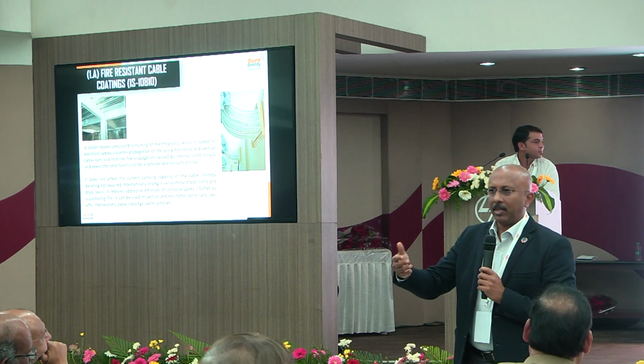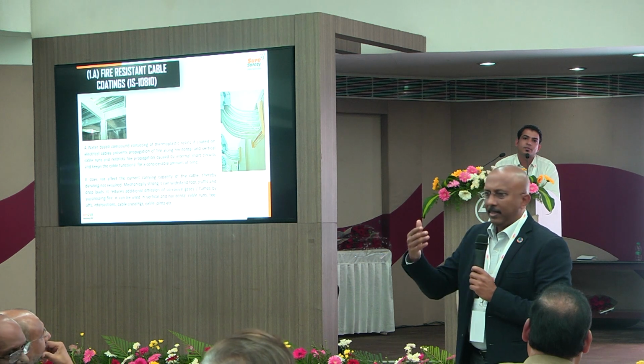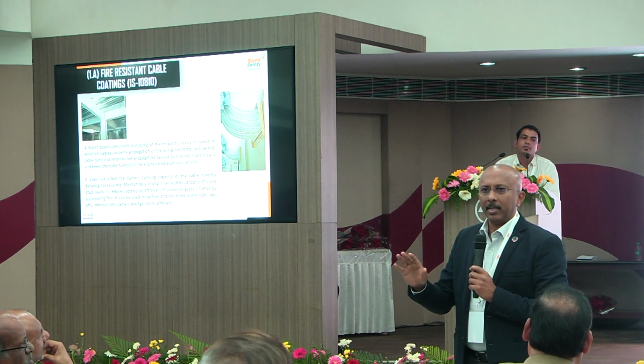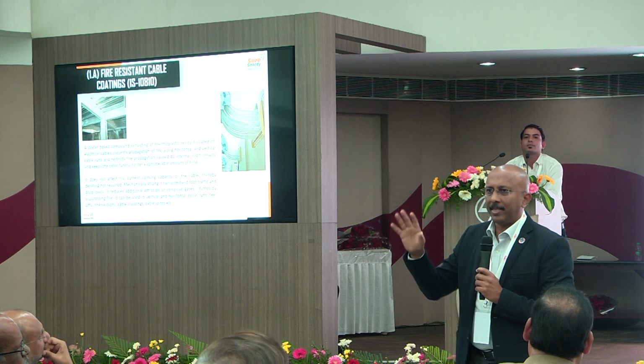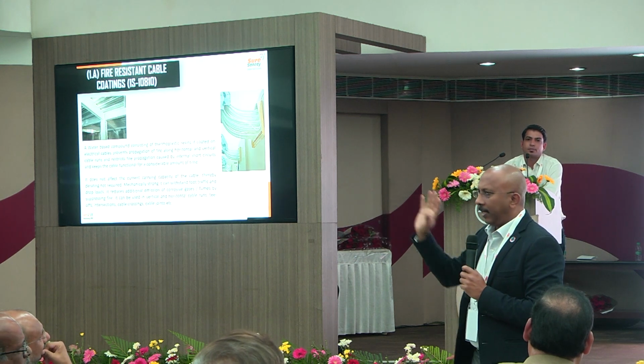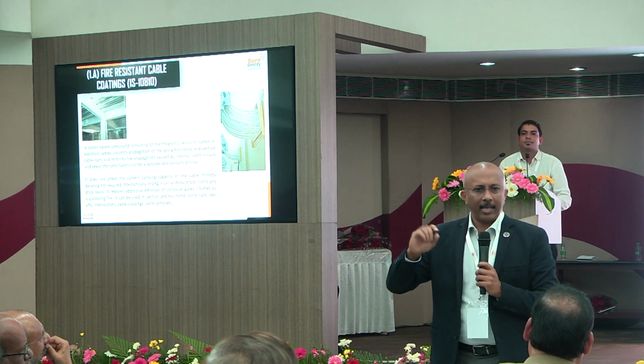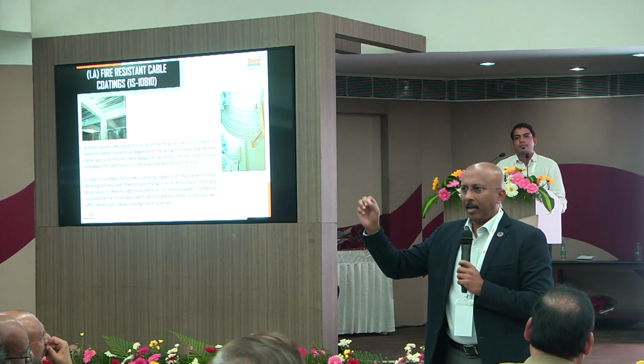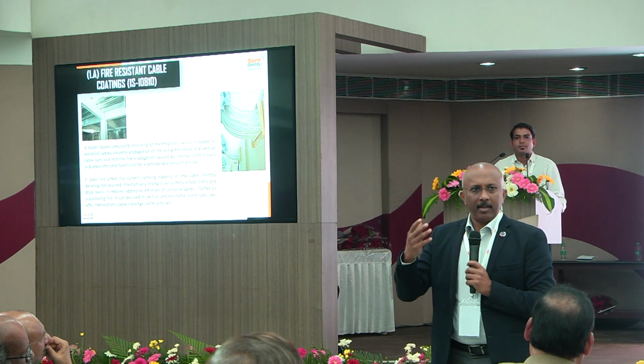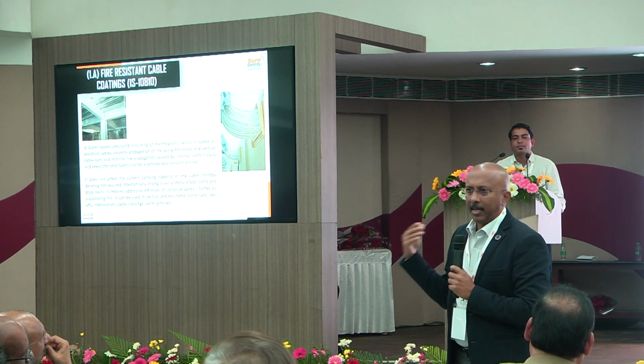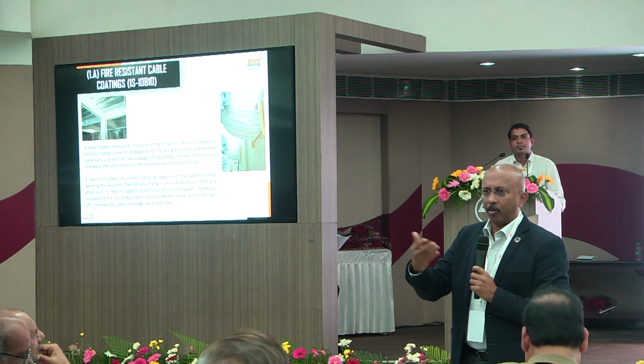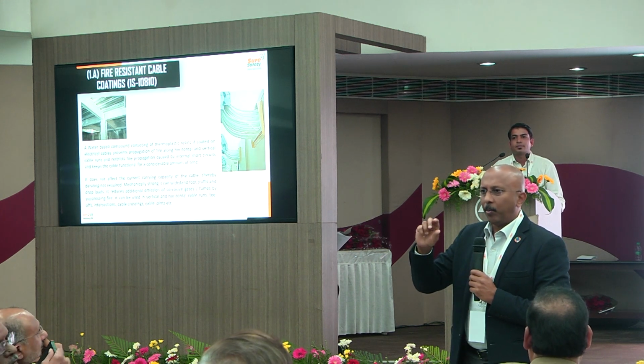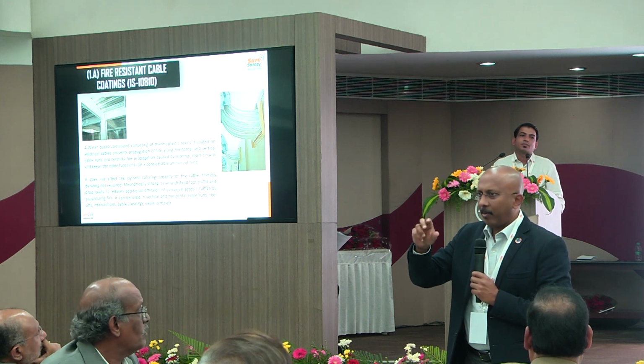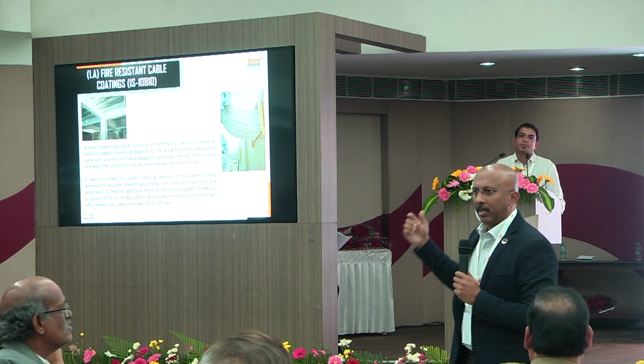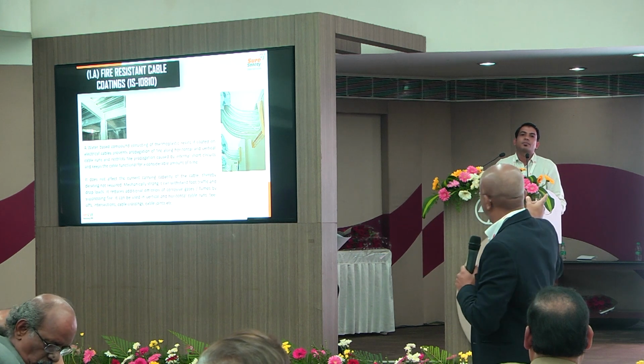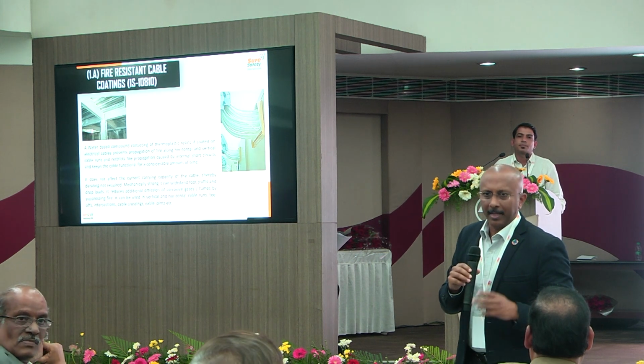Those tests, since our standards are coming from IEC, do not consider whether it is FRLS, and all these fancy names are not there. There is a standard referred, and all cables used are supposed to be tested according to this standard. But in future, if you want to comply with the NEC, then those cables shall be used. At the moment, these requirements are sometimes not satisfied. As a solution, the same performance can be achieved by this paint. Yes, something like that.